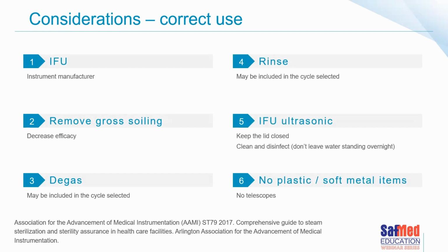Starting off with knowing that the device that you're about to process in the ultrasonic cleaner can actually go in the ultrasonic cleaner, or is meant to go in an ultrasonic cleaner. It always helps to remove gross soiling, which means a pre-rinse, because a lot of soiling can decrease the efficacy of the cleaning, so a point to consider. Degassing is an important process. Some machines are automated and will include degassing as part of the cycle. Others won't, so an important point to bear in mind.